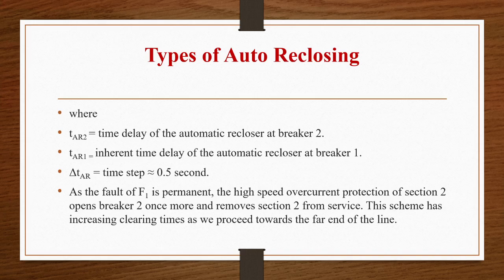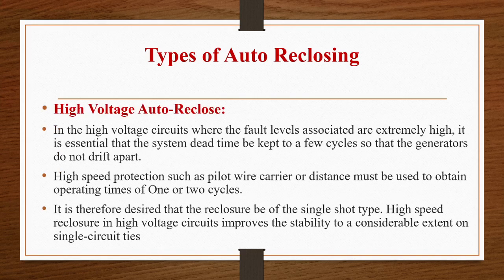Now what is this delta TAR? Delta TAR is the time step, that is approximately equal to 0.5 seconds. As the fault F1 is permanent, high speed overcurrent protection of section 2 will open circuit breaker 2 once more and remove section 2 from service. So this scheme has increasing clearing time as we proceed towards the far end of the line.